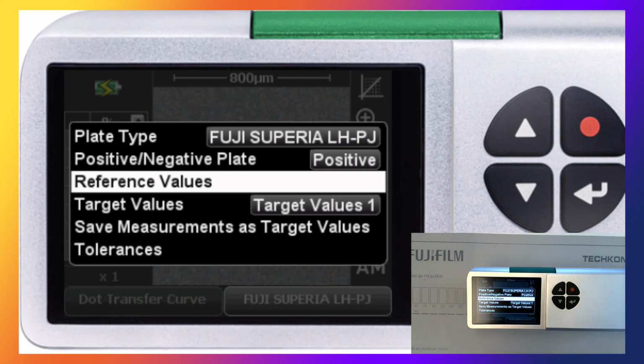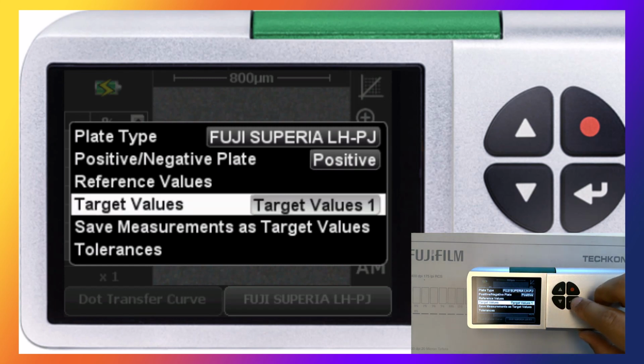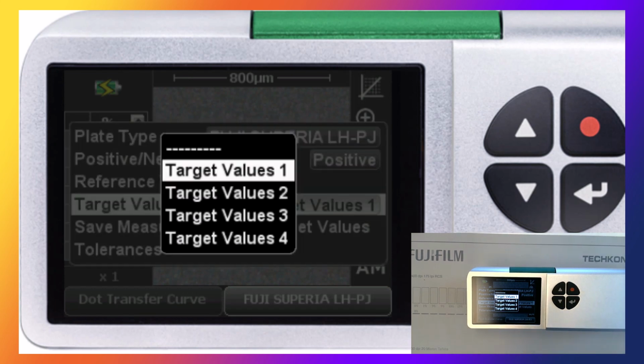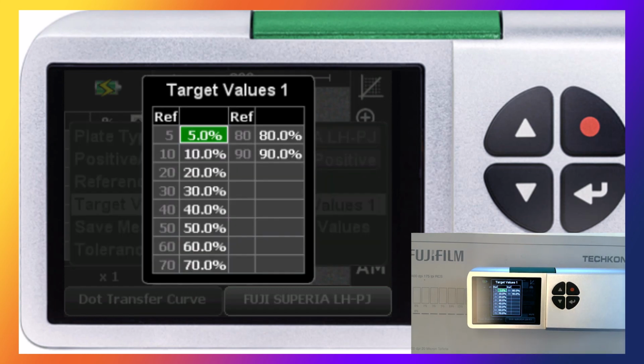Once we have our reference values all set, we can go to the target values. This device allows us to have up to 4 different target value sets, and I'm going to the first one. The target values are the ideal or wanted dot measurement target you're trying to achieve.